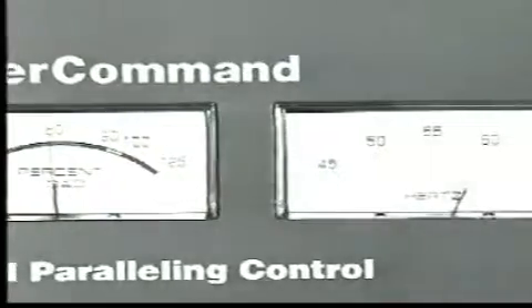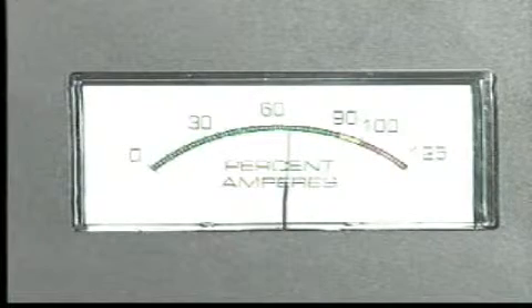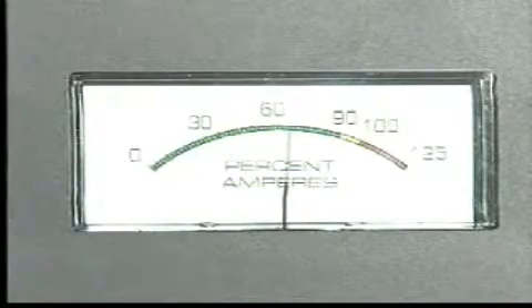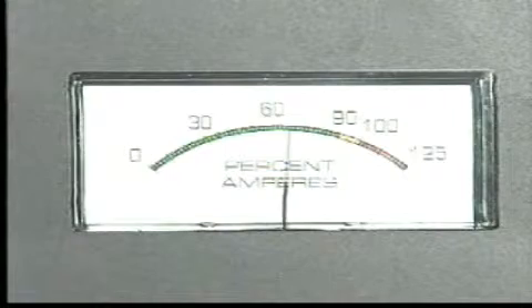As this is a microprocessor control with digital display, you may wonder why the analog meters? Why both analog and digital? Watch this. The analog meters show generator set transient performance conditions as they happen. The kilowatt meter and ammeter are scaled in percentage for instant indication of status and load level. The digital displays provide precise readouts for each of these functions.